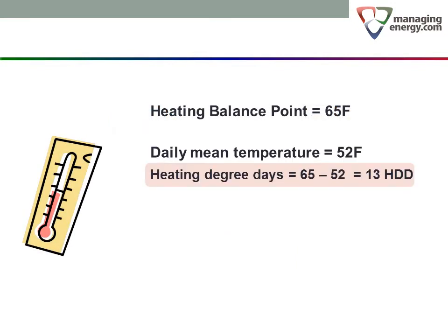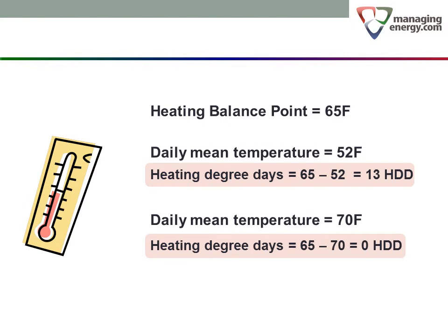Heating degree days are units of outdoor air temperature over time used as a measure of heating load. The HDD value for a single 24-hour day is the difference between the daily mean temperature and the heating balance point when the outdoor temperature is below the balance point. When the daily mean temperature is above the heating balance point, there is no heating load, so the HDD value is zero. The HDD value for any period is the sum of the heating degree days for all the days in the period. In this example, the heating balance point is 65 degrees Fahrenheit. A day with a daily mean temperature of 52 degrees Fahrenheit would yield 13 heating degree days. If the following day has a daily mean temperature of 70 degrees, the heating degree days would be zero. The cumulative heating load for the two days would be 13 heating degree days.